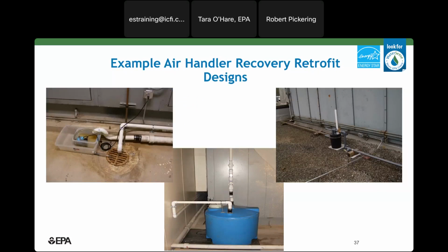The biggest challenge with this type of project is the plumbing required to get water from the air handler condensate line to the cooling tower. However, if the pipe runs are not too long or complicated, and you don't need to make too many wall intrusions, that can make the project very cost effective. There are a few example designs that have been incorporated in some of the facilities that I'm familiar with. As you can see, these projects don't really need to be that complex or complicated. They can just involve something to catch the water, a submersible pump to pump it away, and the piping to get to the cooling tower basin.